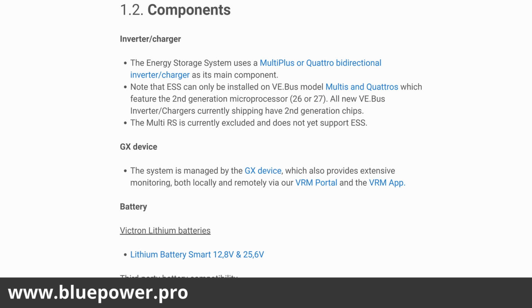You can also run ESS on the new Multi RS inverters. You're also going to require a GX device to be able to configure any of the ESS settings and so forth, and for any remote monitoring on the Multi RS, but it has a basic setup for ESS operation just from the Bluetooth app, which you can configure without the GX device, and then that will operate just as a standalone Multi RS in ESS operation. It can also be set up to intentionally island the Multi RS. So a GX device is required for the Multi or Quattro. That can be monitored locally via the VRM app or remotely via the VRM portal.